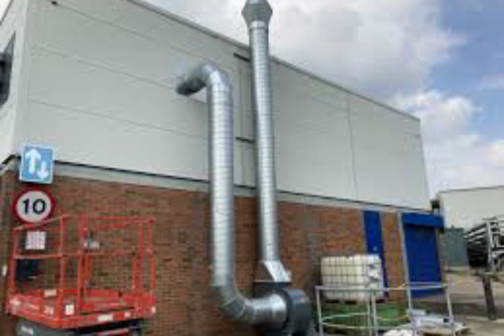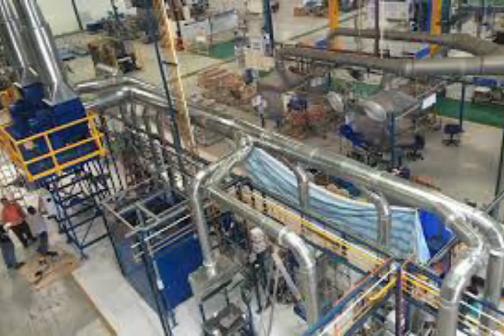Next, effectiveness of the LEV system is reduced by: number 1, poor intake hood position; 2, damaged ducts; 3, excessive amount of contaminants; 4, ineffective fan due to low speed; 5, blocked filters; 6, buildup of contaminant in duct; 7, sharp bends in ducts; 8, unauthorized addition to the system.